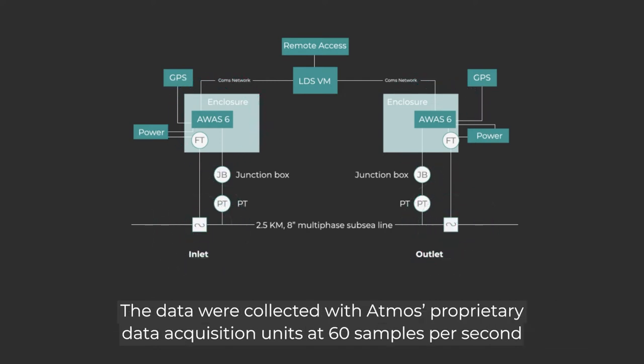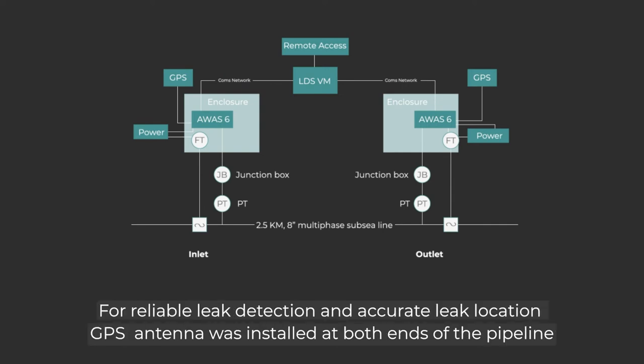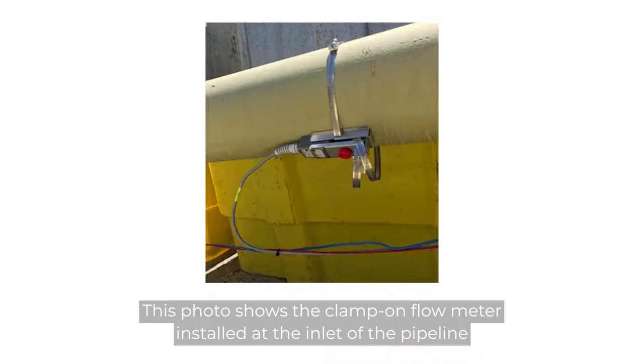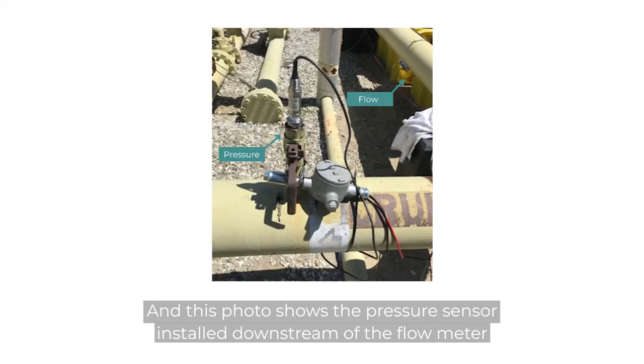The data were collected with Atmos proprietary data acquisition units at 60 samples per second. For reliable leak detection and accurate leak location, GPS antennas were installed at both ends. This figure shows the instrumentation system setup for this application. This photo shows the clamp-on flow meter installed at the inlet, and this photo shows the pressure sensor installed downstream of the flow meter.